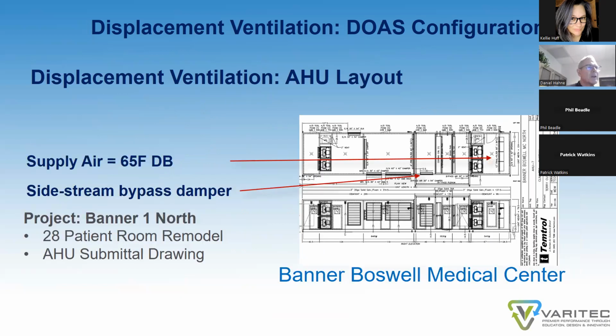Here's a design of a configuration we used with a displacement system in a Banner Boswell Medical Center. I don't know that I would recommend this configuration in a 100% outside air system. This uses a property called side stream bypass, where mixed air is injected into the supply air stream after the cooling coil as well.